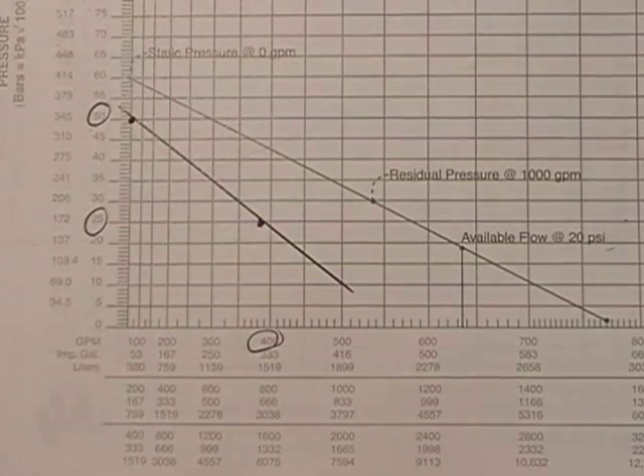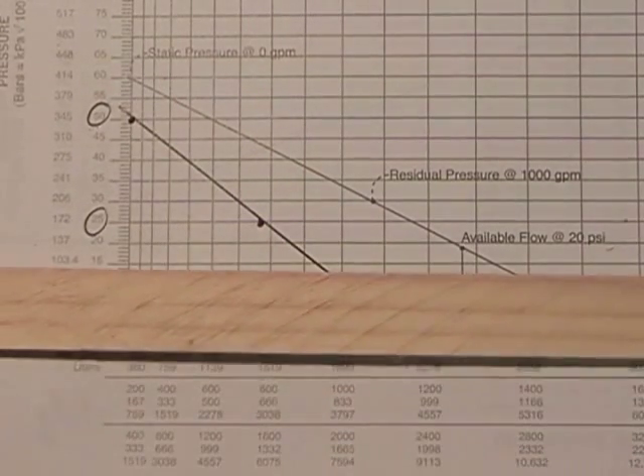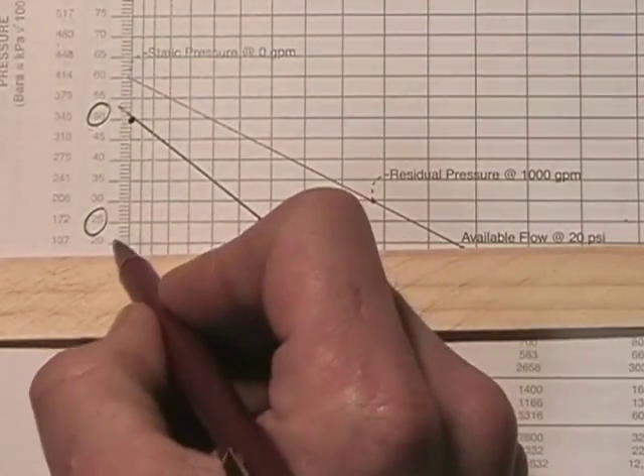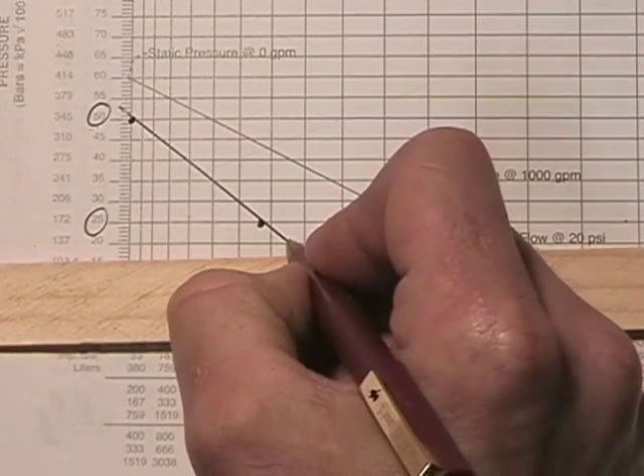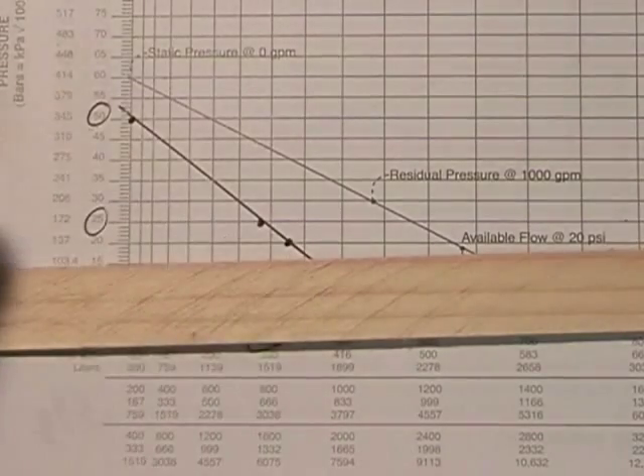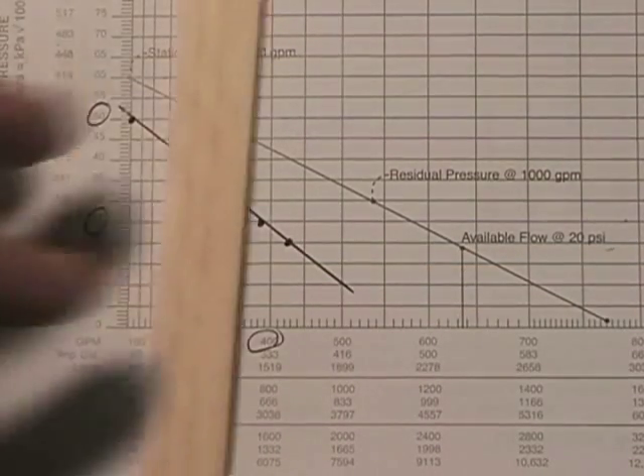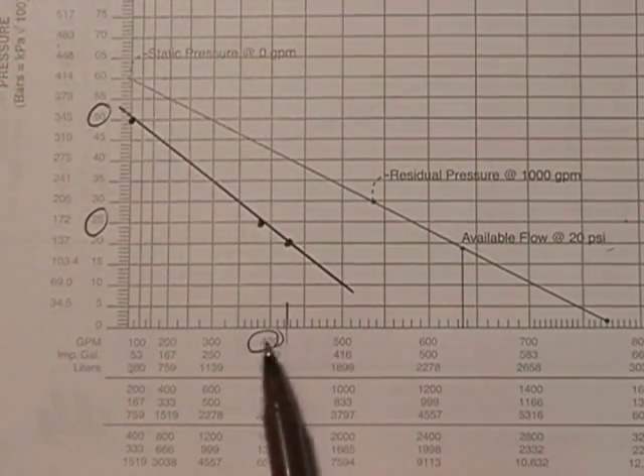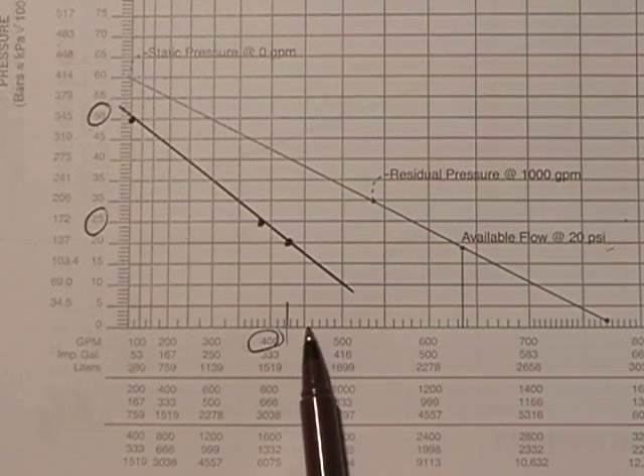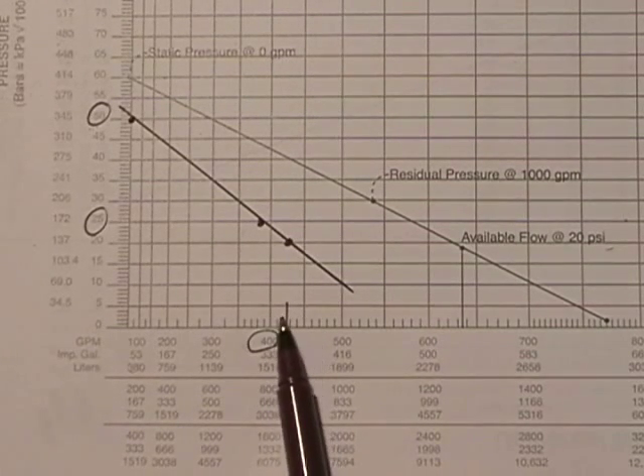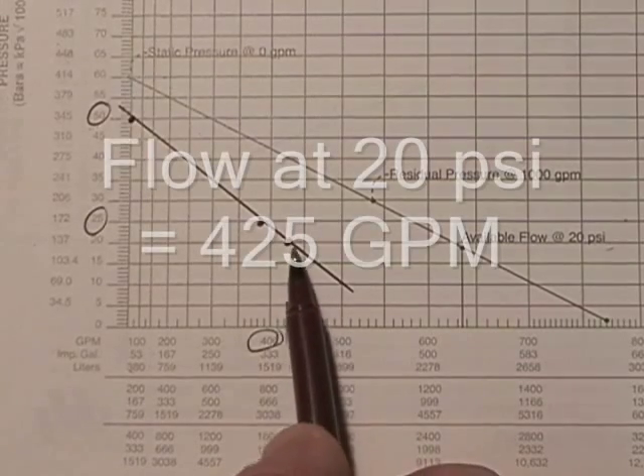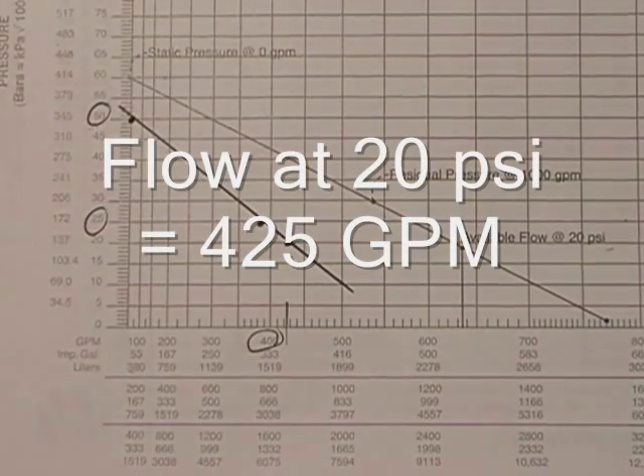When we do that, we're going to end up crossing the 20 psi line. The 20 psi line right here is going to tell us where, theoretically, if we were to continue to flow even more, we're going to end up at 20 psi. Then all we have to do is carry that down to where it crosses the gallons per minute line. We already know that here's 400, this line would be 450, so we're very close to the center. So estimating our 20 psi flow would be about 425 gallons a minute.